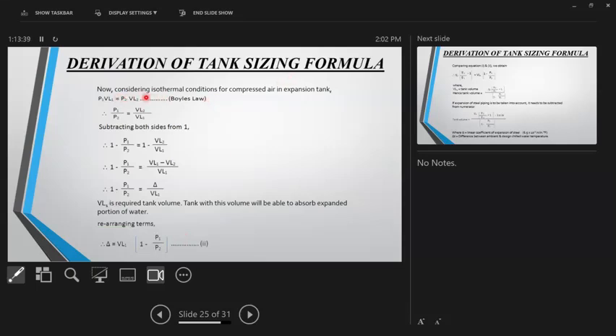Now, the air or nitrogen in the tank bladder, you can actually apply Boyle's law. Boyle's law can be applied only when there are isothermal conditions, theoretically. But here we are saying the chill water temperature is changing from 7 to 30. However, for the air, you can assume the temperature rise to be minimal because air and water are separated by a bladder, which is a thick rubber bladder.